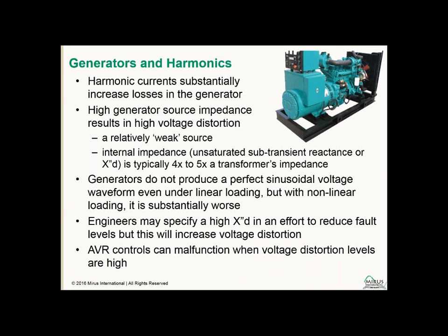So harmonic currents substantially increase the losses in the generator, and this is due to many reasons, but partly because the harmonics introduce stray magnetic fields, which result in excessive eddy currents in the generator's windings and in the laminations, and those will increase the losses. And also there'll be increased I²R losses due to the skin effect, with the higher frequency harmonic currents tending to flow on the outer edges of the conductors.